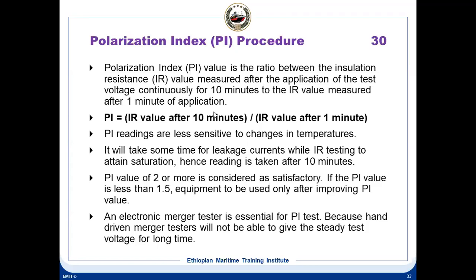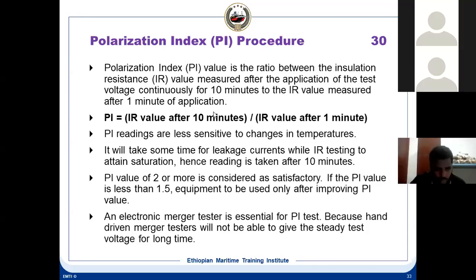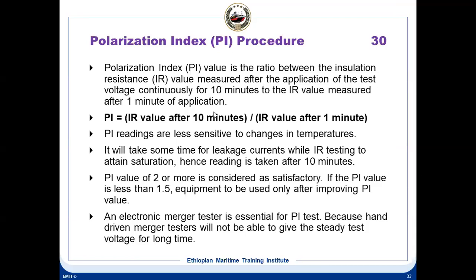Now, how do you improve the PI value? You can heat up the winding or revarnish the winding, then the value can be improved. Because basically the PI insulation test is only to check the moisture content, the dryness, and the winding condition. So if we find the PI index value is dropping below 1.5, then you have to improve the winding condition by heating up, revarnishing, or rewinding. This has to be done. An electronic Megger is essential for the PI test because a hand-driven Megger will not be able to give a steady test value for a long time.